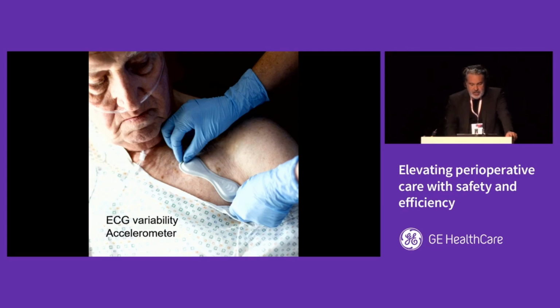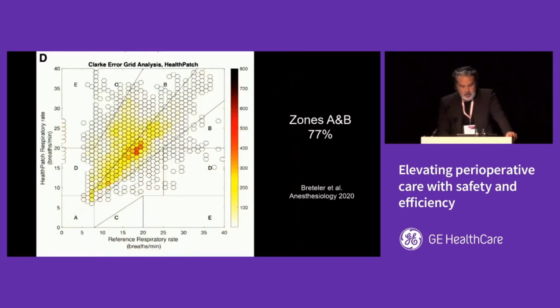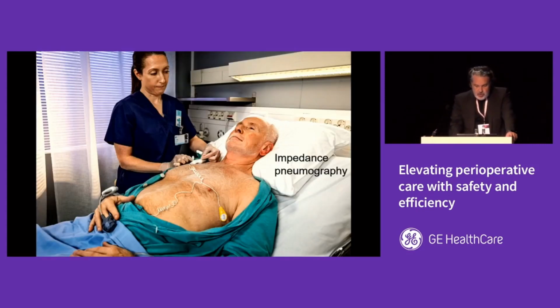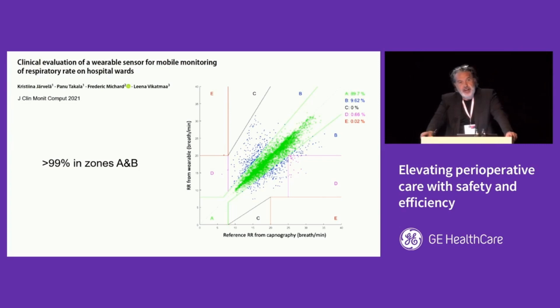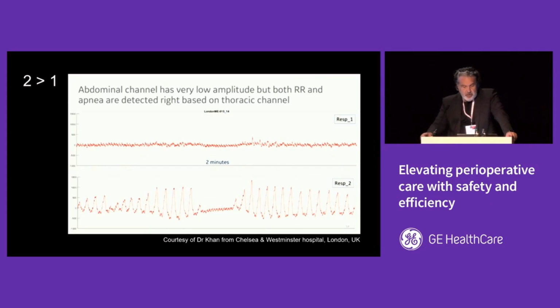This is an adhesive patch using ECG variability and accelerometer data to compute respiratory rate. And this is a so-called validation study using a reference method on the x-axis. And you see that only 77% of the measurements were in the safe zones A and B of the Clarke Error Grid. This one is a different system with 3 electrodes using impedance pneumography. It's a wireless system. And you see the same kind of validation study, this time with over 99% of measurements in the safe zones A and B of the Clarke Error Grid. But just to highlight that all systems have not been created equal. The reason why this system is working pretty well is probably because when you have 3 electrodes, you have at least 2 signals. One could be an abdominal signal and the other one a thoracic signal. So if for any reason, like in this example, you don't get the information from the abdominal signal, very likely you will get it from the other one.